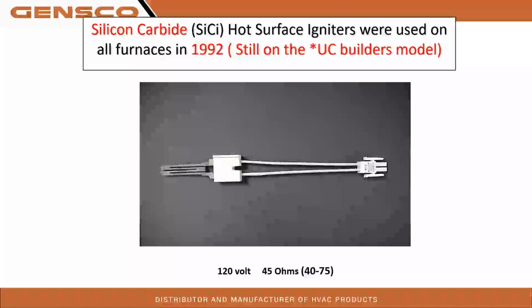Okay, so silicon carbide hot surface igniters we've used on furnaces since '92. We still use them on the UC Builders models. Obviously, we're phasing out the 40-inch cabinets. It's carbide, so you never want to touch the carbide aspect of it. Insulator touch only. It's a 120 volt unit. It's 45 ohms at room temperature. 40 to 75 would be the working range at room temp.